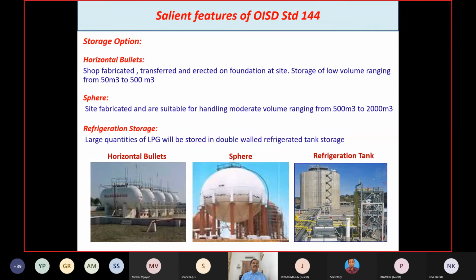And the LPG storage options. The horizontal bullets are there. If you want to store a low volume, ranging from 50 meter cube to 500 meter cube, you can go for horizontal bullets, which can be fabricated in the workshop, transferred and erected on foundation at site itself. Then the sphere: we should fabricate it at the site itself, and it cannot be transferred from one place to another, and it is suitable for handling moderate volume, ranging from 500 meter cube to 2000 meter cube. For refrigerated storage, if you want to store large quantities of LPG, about 10,000 to 15,000 metric ton, it is best to store it in a double walled refrigerated tank.